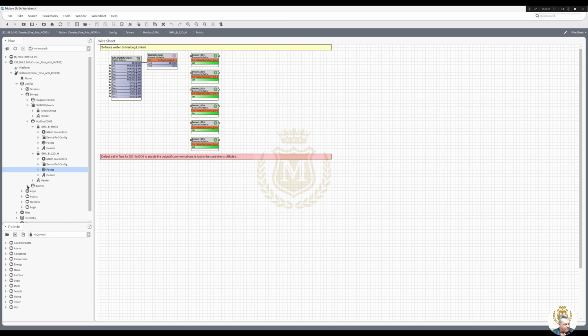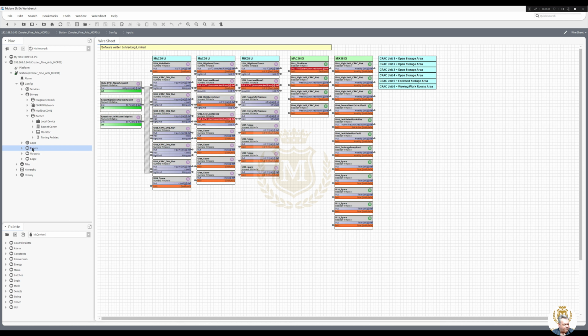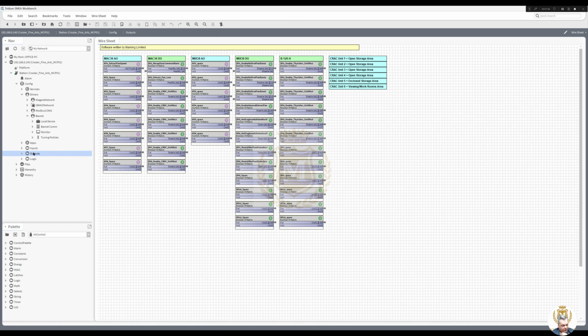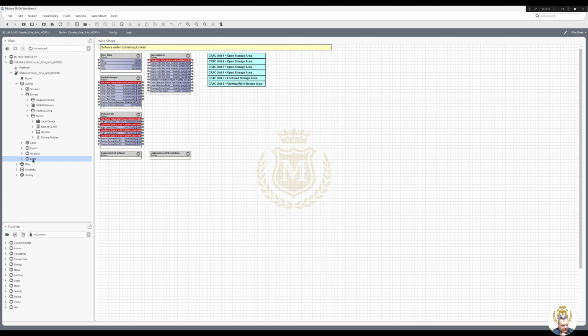And then BACnet, I've done nothing with BACnet because I'm not on site, so I can't discover the units, and it's been a while since I've done a CRAC unit before. So they're all my inputs for the CRAC units, and for all what's on the panel drawings. They're all my outputs, and that's my logic that I've done at the moment.